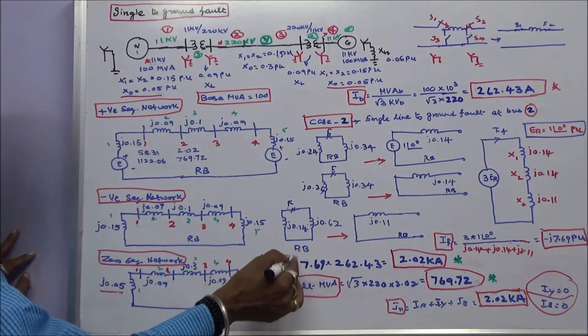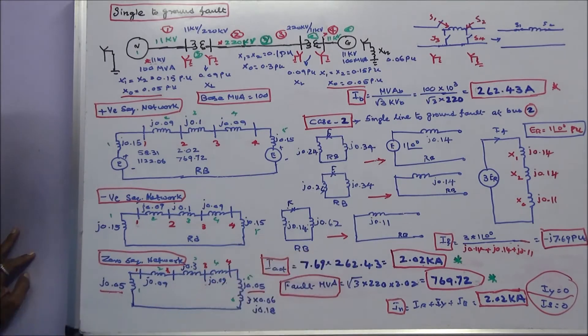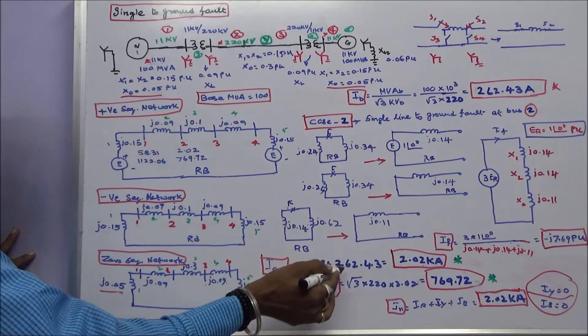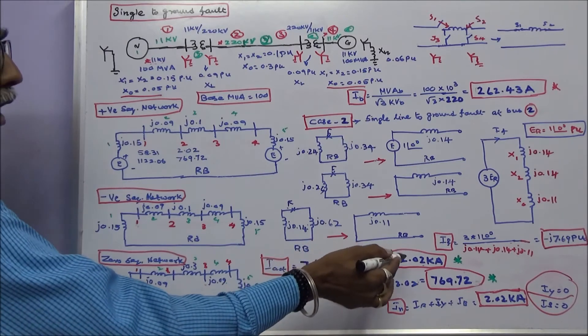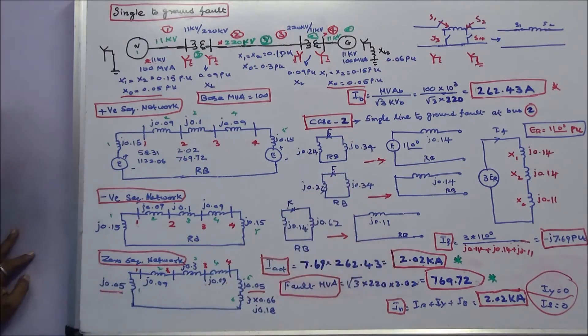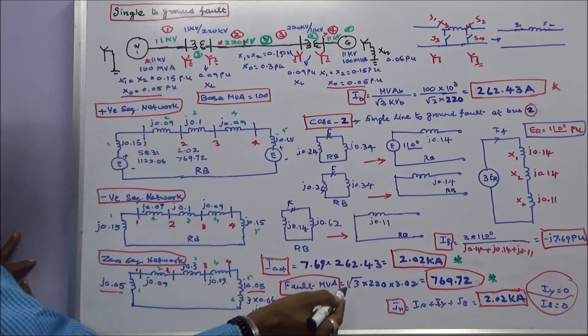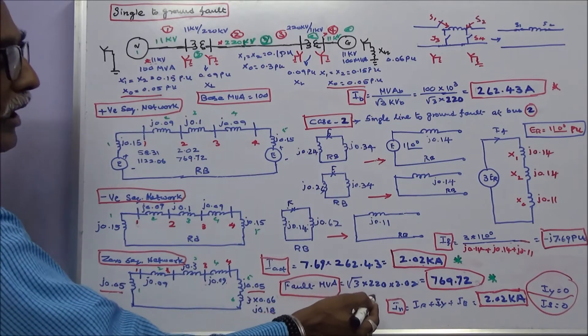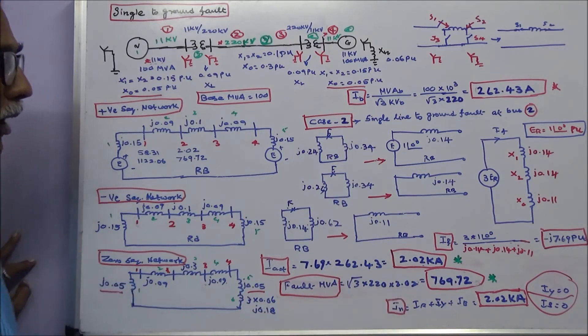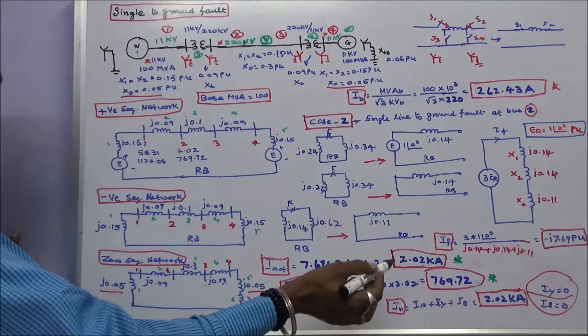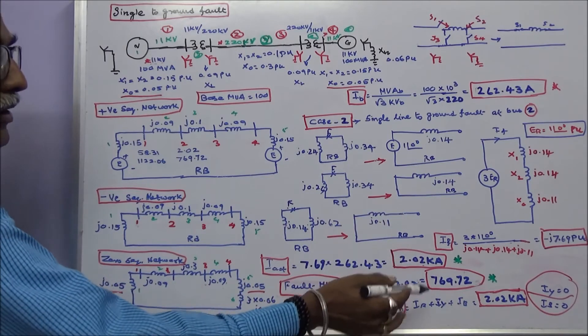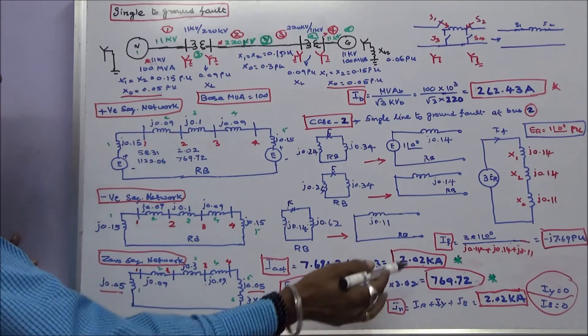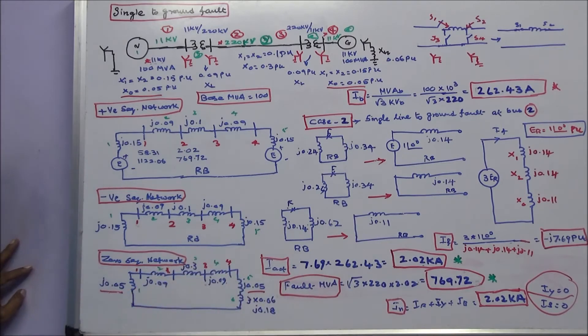Actual fault current is 7.69 times base current 262.43, equaling 2.02 kilo amps. Fault MVA equals root 3 times 220 times 2.02, giving 769.72. Neutral current: IY equals 0, IB equals 0, IR equals 2.02 kilo amps.